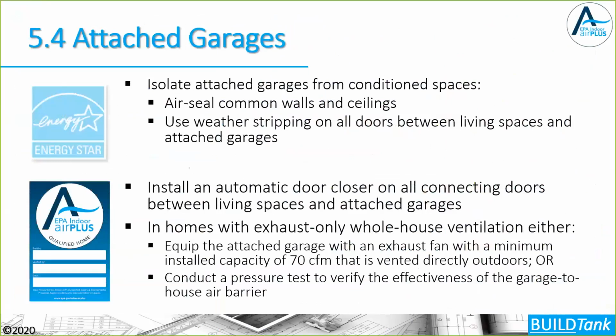So this just reviews what we just talked about to ensure that we have the system there. If you're testing the house, you have to have a fan located in that garage that can depressurize that garage. Usually a 70 CFM fan can do that, and then you conduct the pressure test. Now that pressure test used to be required regardless of whether you used option 1 or option 2. Now it's only a mandatory requirement if you're using option 2 here with the exhaust fan, but you'll see a lot of folks continuing to use the test regardless of whether they use option 1, this isolation method, because it turns out that you only get what you inspect, not what you expect.